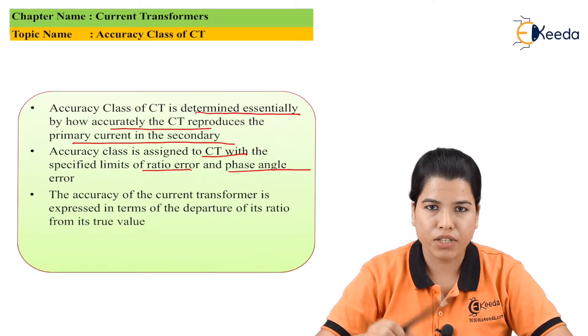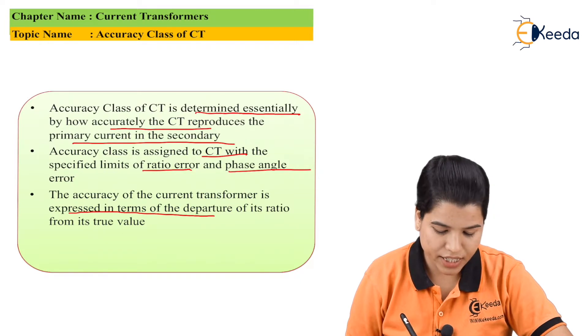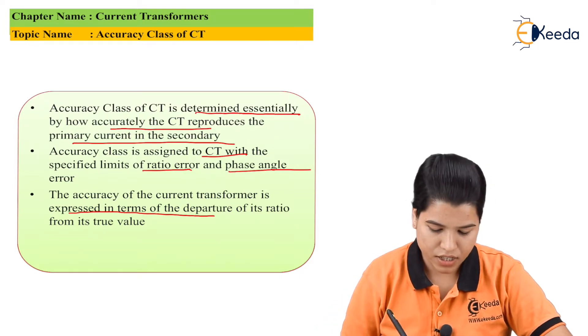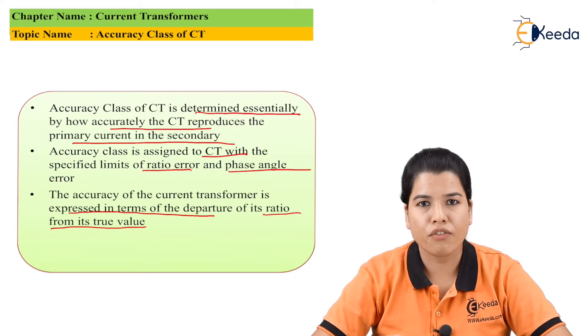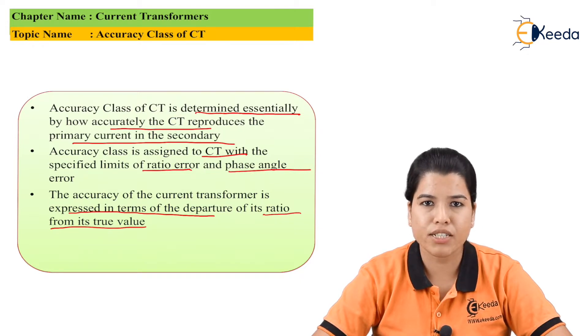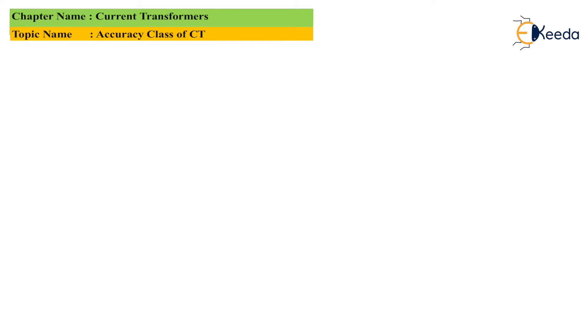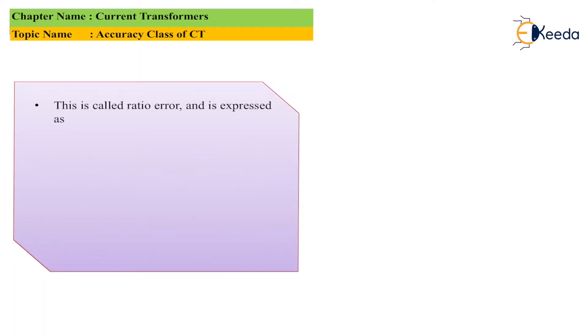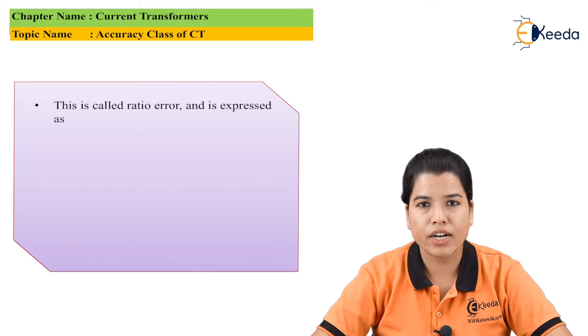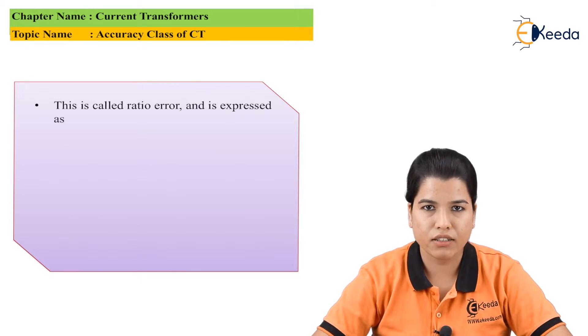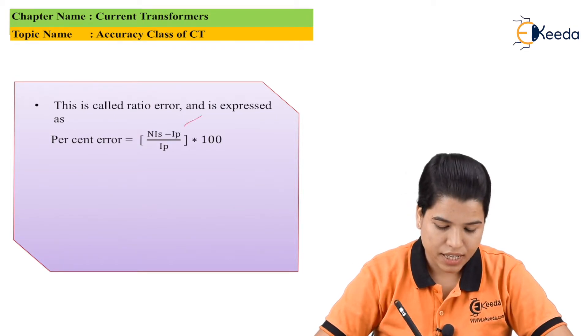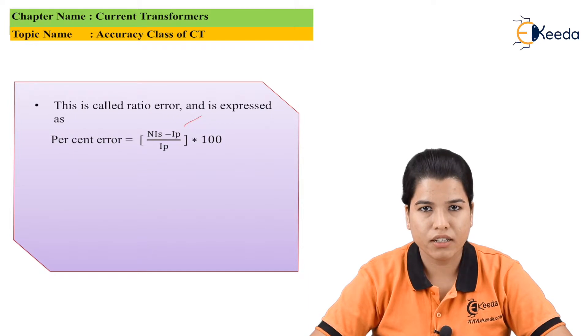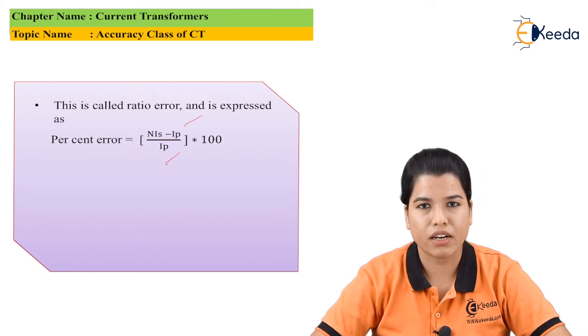The accuracy of a current transformer is expressed in terms of departure of its ratio from its true value. Whether there is a departure of the ratio from the true value to the actual value — depending on that, the accuracy class of the CT can be specified. This phenomenon is basically called the ratio error, and it is expressed by the formula: percentage error = (N × Is − Ip) / Ip × 100.